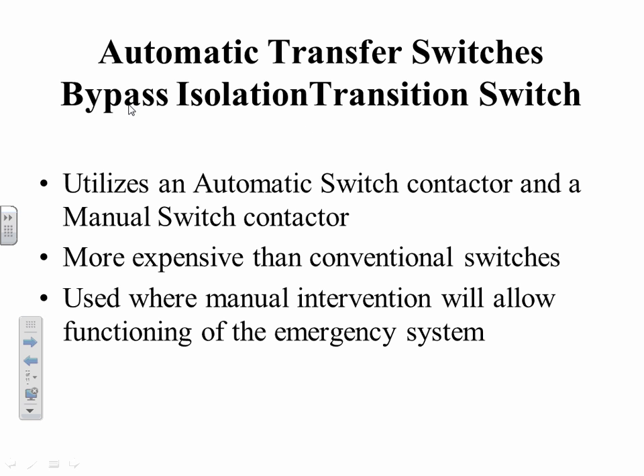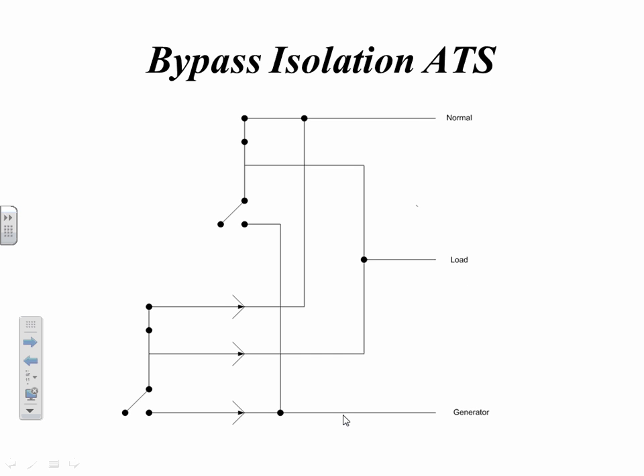The main reason for a bypass isolation transfer switch is it's used where manual intervention, in other words, you've got an operator there, will allow functioning of the emergency system. When I explain, it'll make more sense. We'll look at the drawing. Okay.